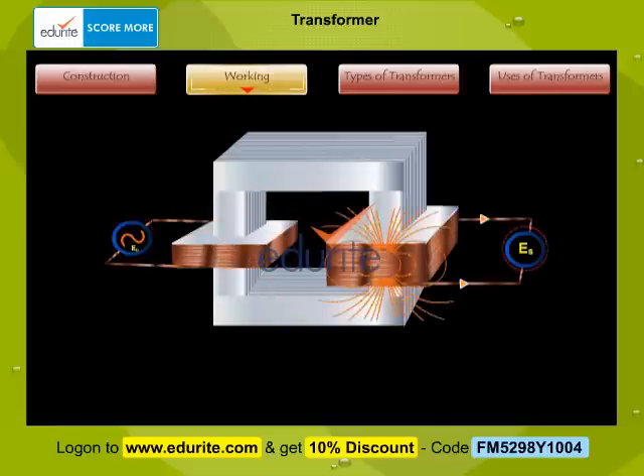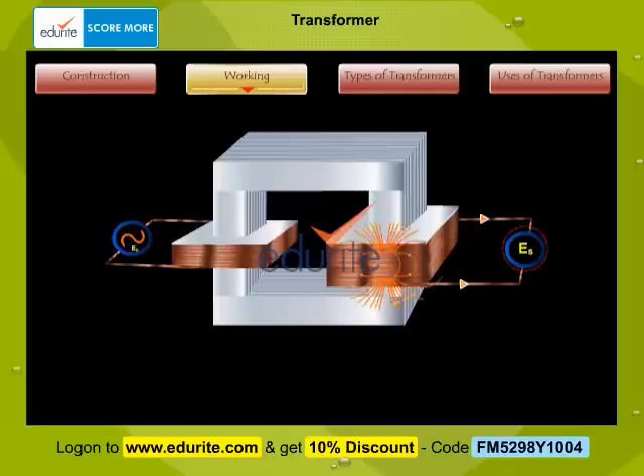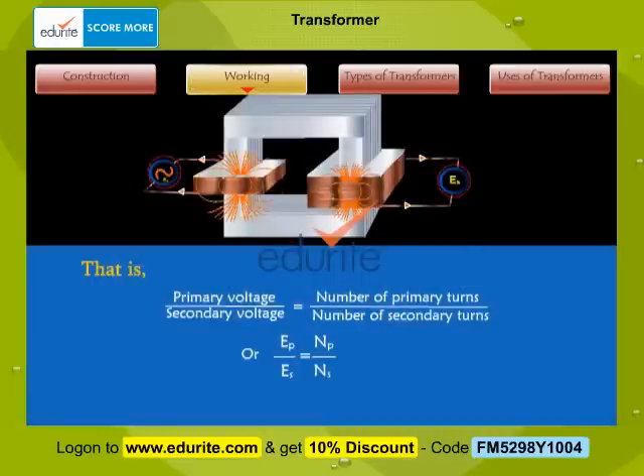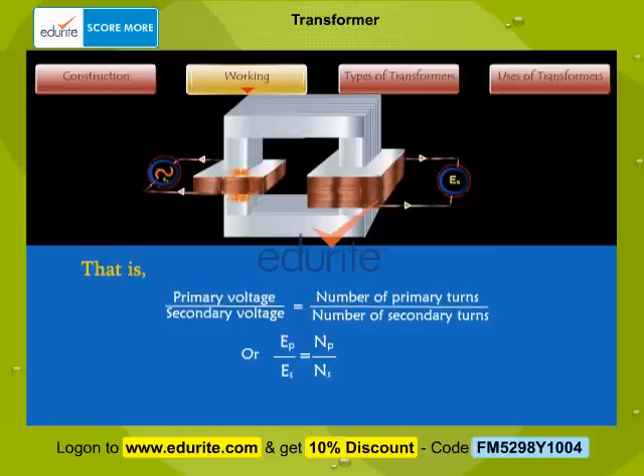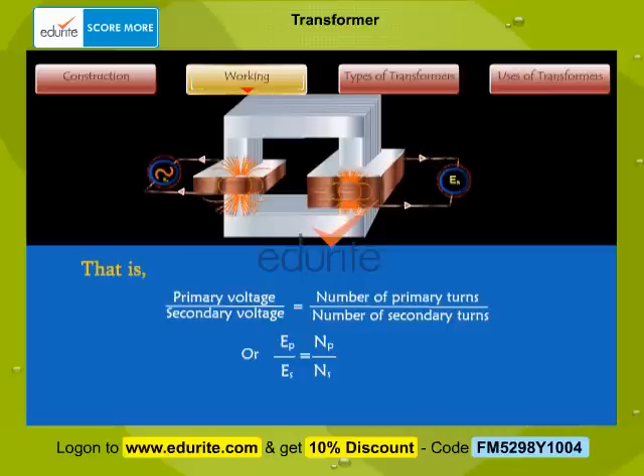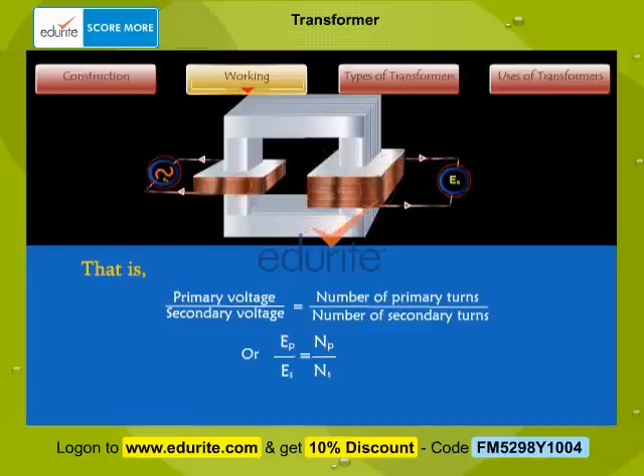Due to mutual induction, an EMF is induced in the secondary coil. The voltage induced in the secondary is determined by the turns ratio — that is, primary voltage divided by secondary voltage is equal to the number of primary turns divided by the number of secondary turns, or EP by ES is equal to NP by NS.